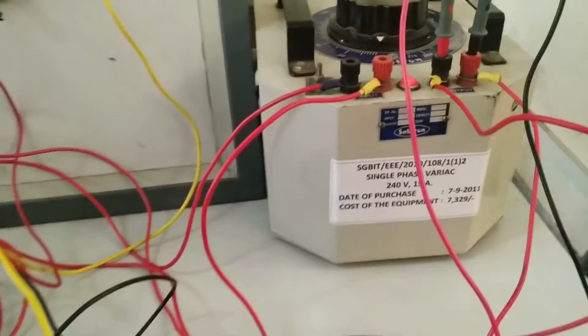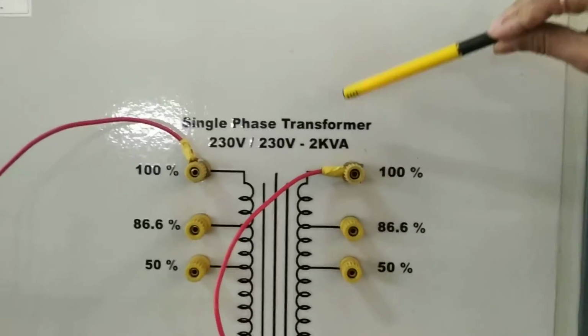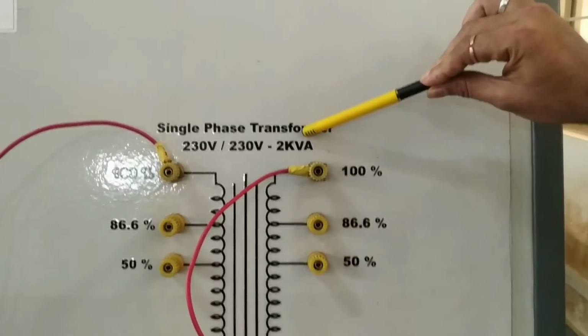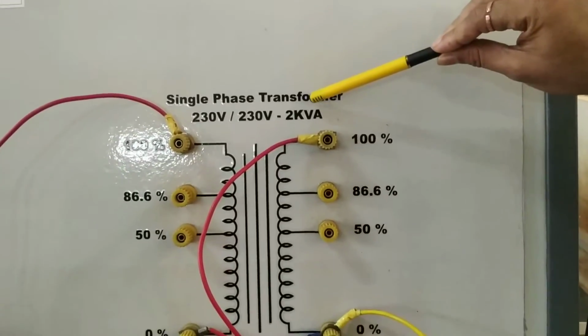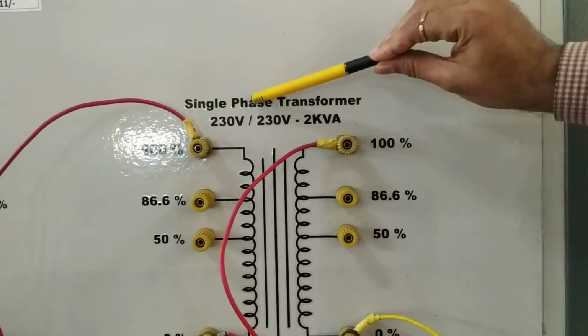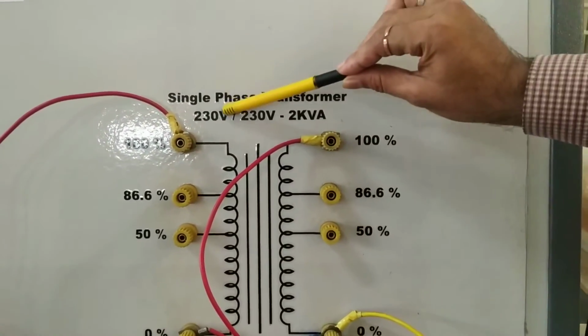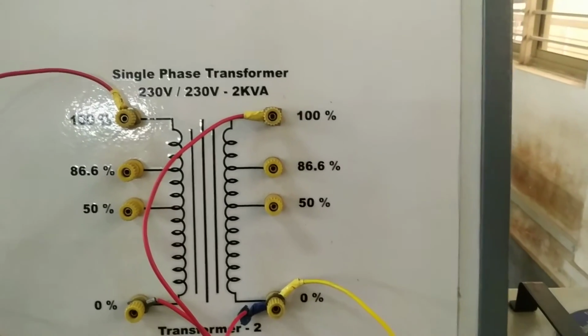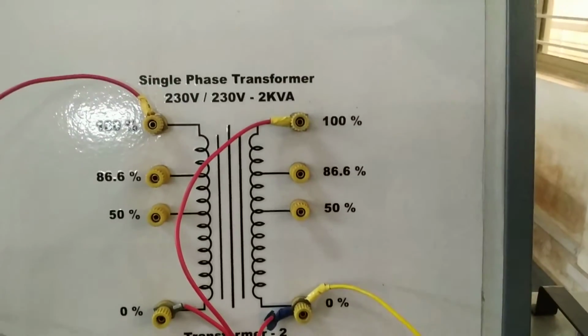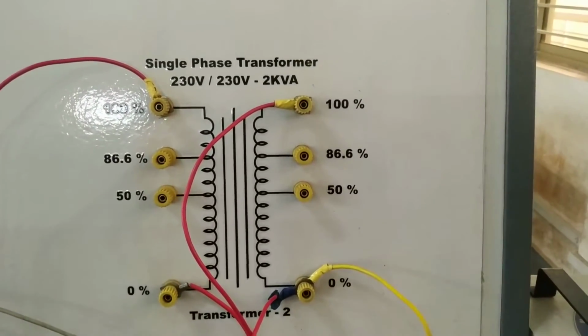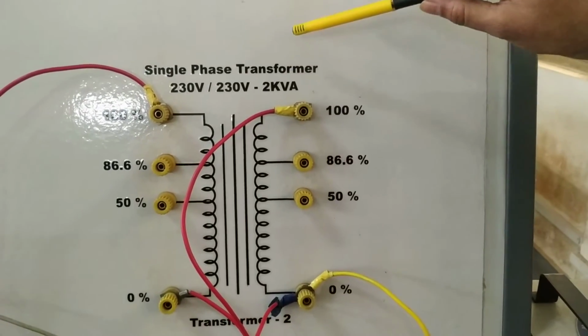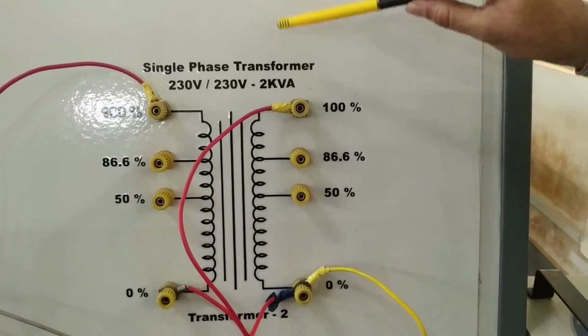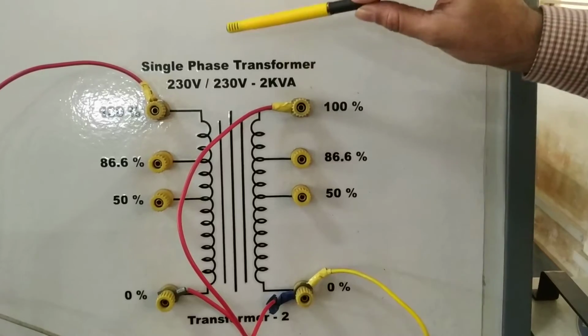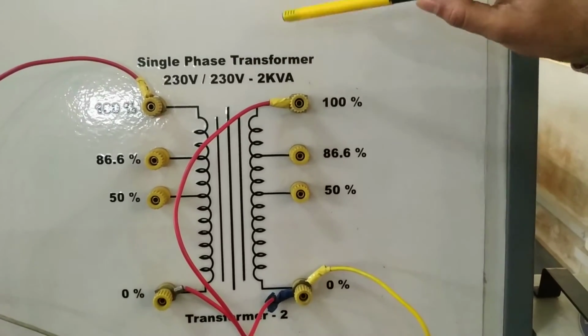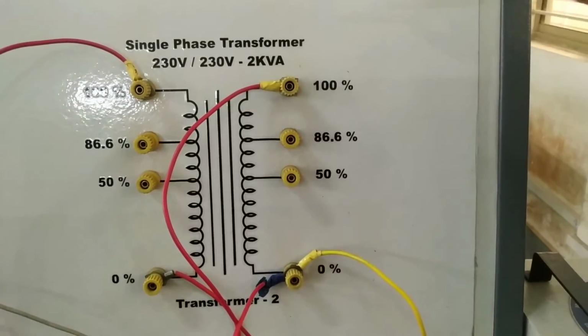The rated current of the transformer can be calculated from the voltage and the kVA rating. Each transformer is 2 kVA, and the voltage of primary and secondary is 230 volt, right? So with the help of this, current is equal to kVA rating into 1000 divided by voltage. So we will get 8.69 for this.